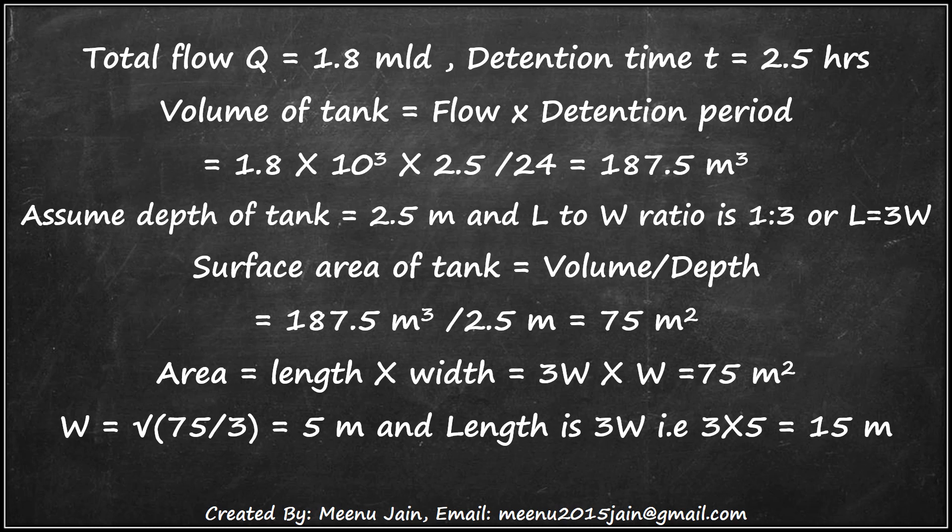Volume equals 1.8 multiplied by 10 to the power 3 — where 10³ is used for conversion of MLD to cubic meters per day — multiplied by 2.5 divided by 24. Here 2.5 is in hours, so dividing by 24 converts hours to days. That gives 187.5 cubic meters.